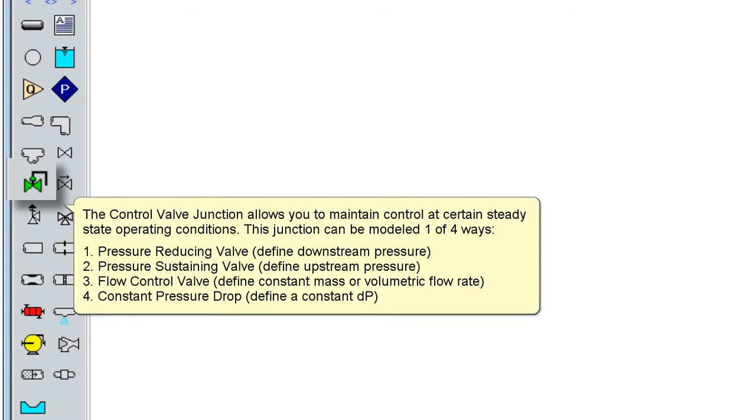a flow control valve, where the user defines a constant mass or volumetric flow rate; or a constant pressure drop, where the user defines a constant delta P, which the valve attempts to maintain at all flow rates.